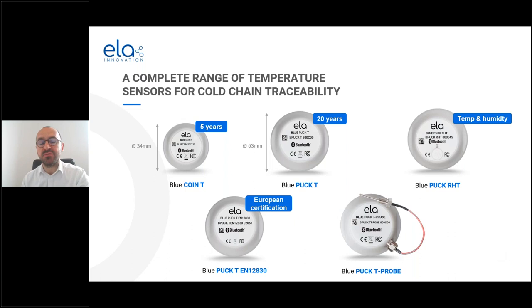This is a requirement from the standards: all recorded values are timestamped, and you also have the possibility to load calibration coefficients inside the sensor so that it can calculate corrected information.